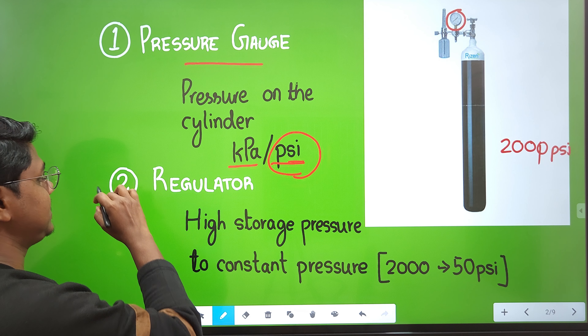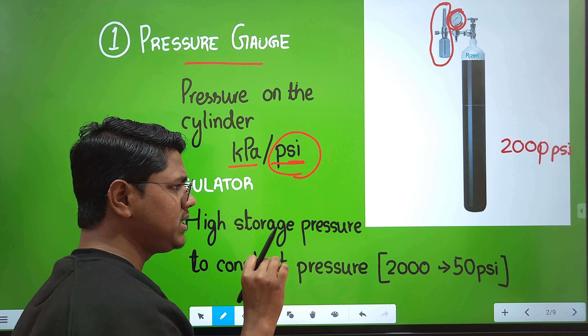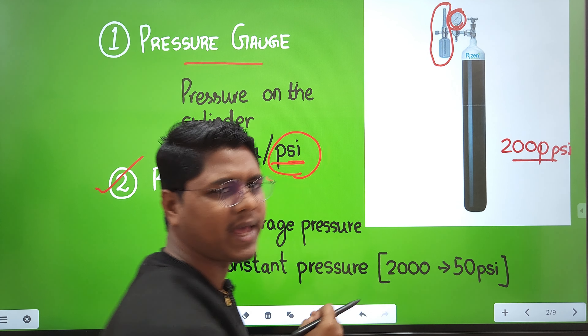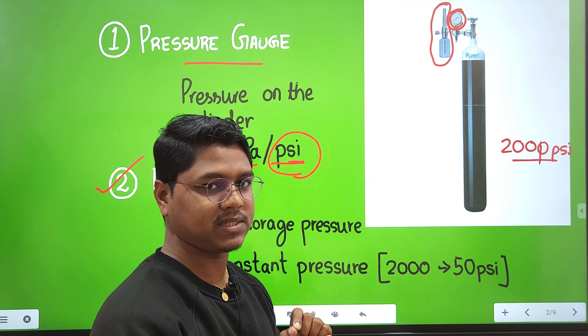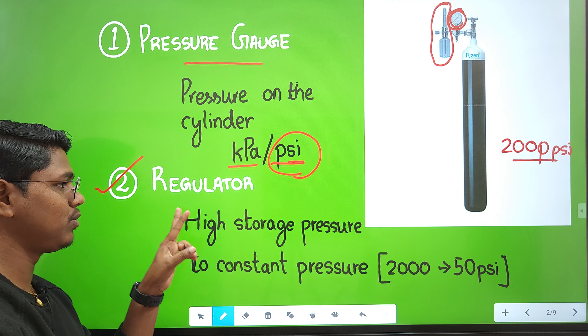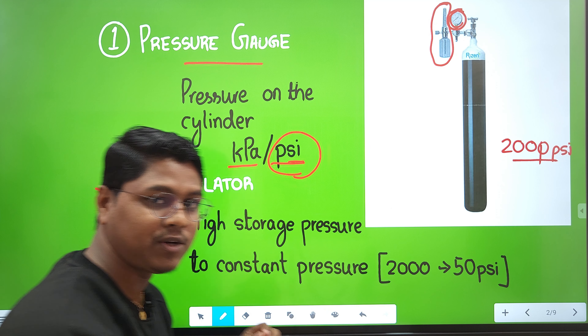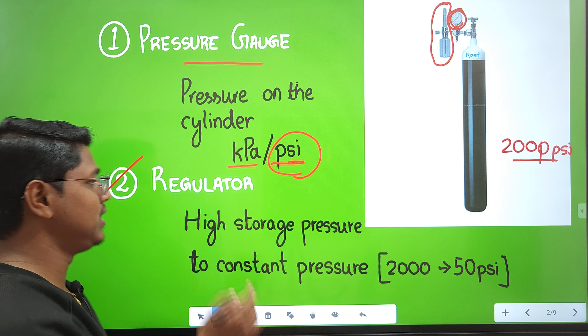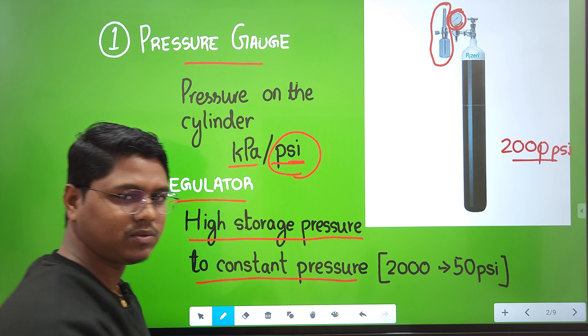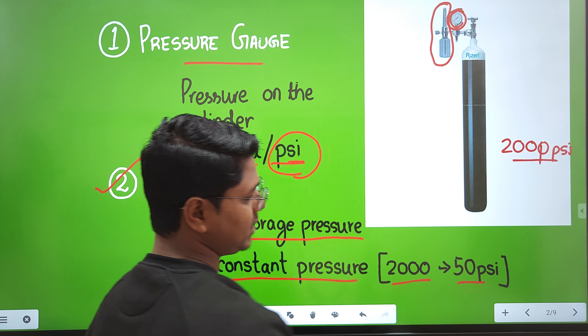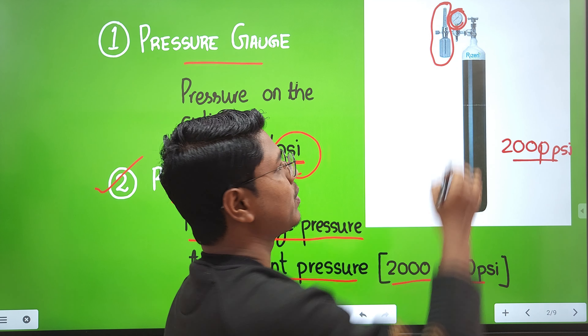The next part is the regulator, located near the pressure gauge. The storage pressure of 2000 PSI is too high to be supplied into the breathing circuit — the correct supply pressure is 50 PSI. The regulator lowers the storage pressure from 2000 PSI to a constant 50 PSI, which is then supplied to the anesthesia machine and into the breathing circuit.